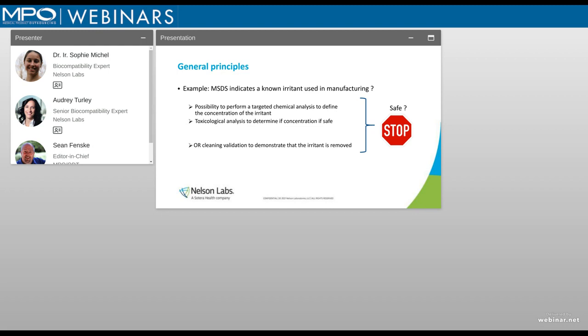Then a way to assess irritation can also be to perform a targeted chemical analysis to define the concentration of this specific irritant, and then make a toxicological analysis afterwards to determine if its concentration is safe to the patient. Another way could be to perform a cleaning validation to demonstrate that the irritant is effectively removed from the final product. And if you are in this situation, then again, it can be that you will not need to proceed through testing.